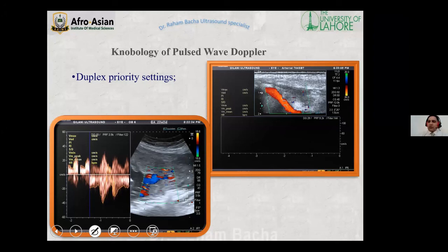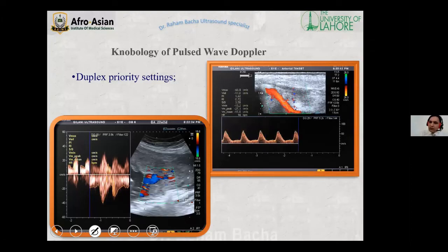So these duplex priority settings are three: simultaneous, intermittent, and dedicated. So here I will show you this one. In the first video clip, you can see the sample volume is placed inside the vessel, but whenever it is updated, the grayscale image is paused at the expense of the spectral Doppler. So now we are having the best spectral Doppler, but the grayscale image is paused.